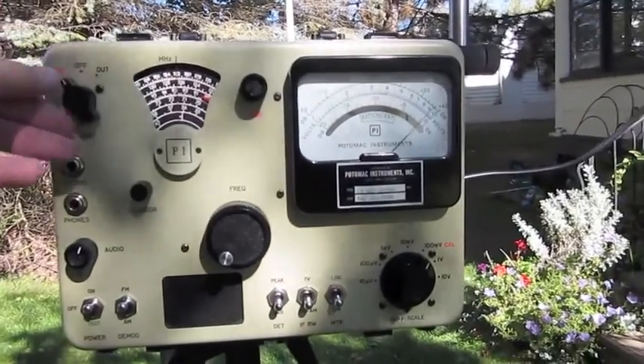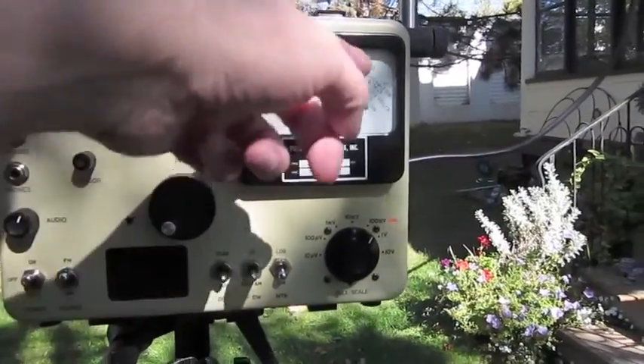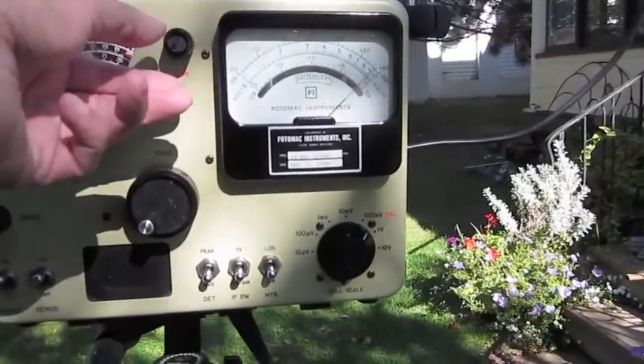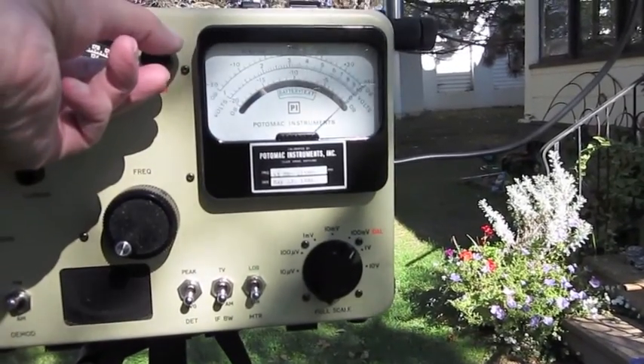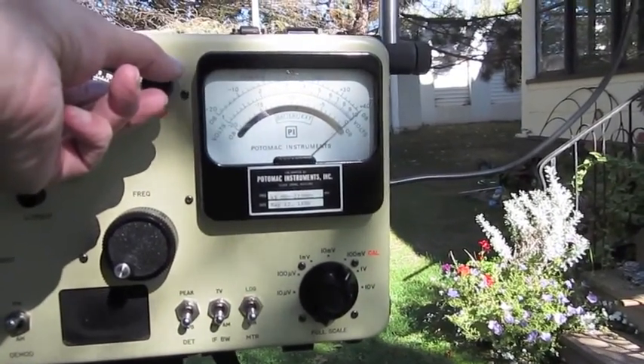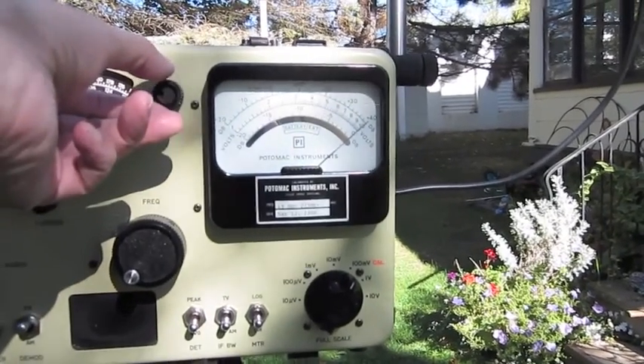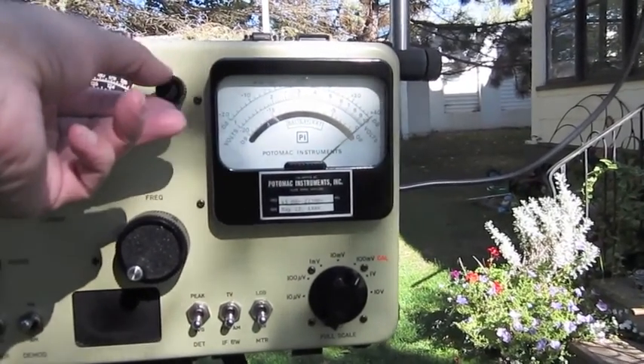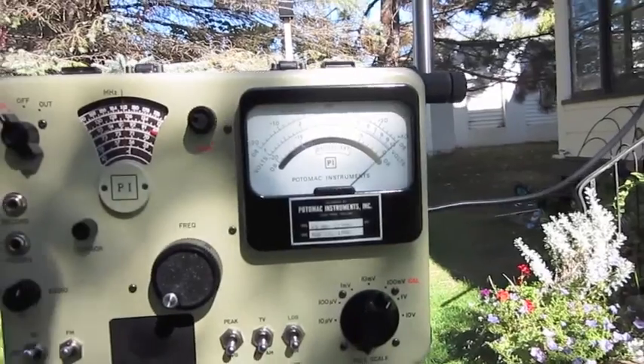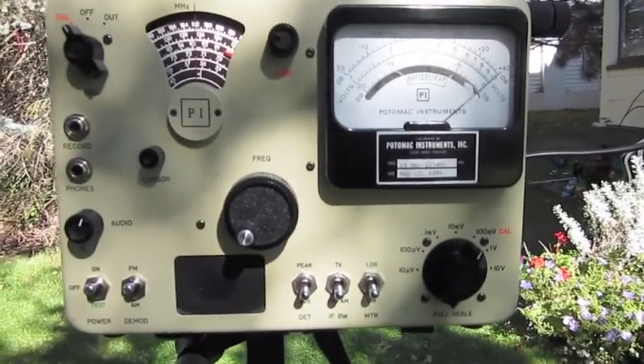We put this on calibrate. It's turned on. You can see we're not quite there, so you tweak this control for exact calibration at 0 dBs, even though we're going to do our readings in millivolts and microvolts. Now you can see we are calibrated right on the zero.